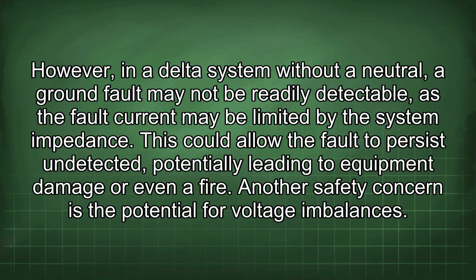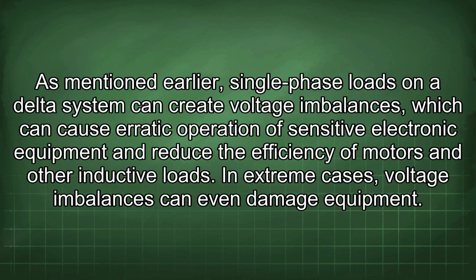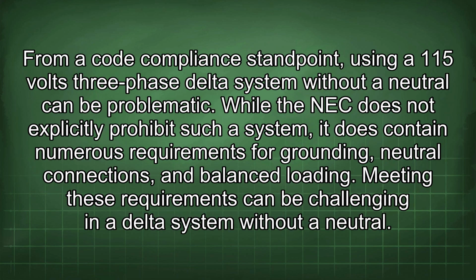Another safety concern is the potential for voltage imbalances. As mentioned earlier, single-phase loads on a delta system can create voltage imbalances, which can cause erratic operation of sensitive electronic equipment and reduce the efficiency of motors and other inductive loads. In extreme cases, voltage imbalances can even damage equipment. From a code compliance standpoint, using a 115 volts three-phase delta system without a neutral can be problematic. While the NEC does not explicitly prohibit such a system, it does contain numerous requirements for grounding, neutral connections, and balanced loading. Meeting these requirements can be challenging in a delta system without a neutral.